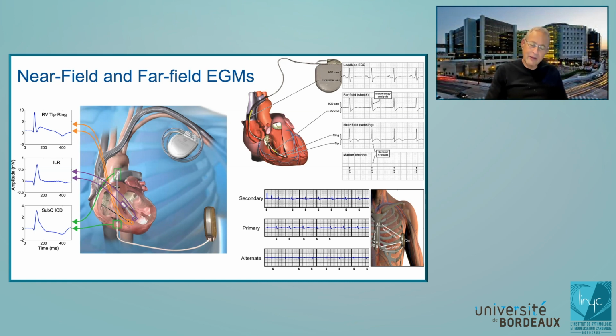But as Pierre knows, I've spent a lot of time working on design of the sensing and detection algorithm for that device. So, Pierre, I apologize, I don't want to exit my slide set to pull up the slides, but that device has two types of electrograms it can sense from. Just to explain to everyone else, so our students know what we're talking about, instead of a device where the electrode sits under the skin, this electrode actually goes just underneath the sternum, but outside the pericardium. The potential hoped for advantage of that device is that it could be used for pacing the heart, even though it is not exactly in contact with the epicardium. It's extrapericardial.